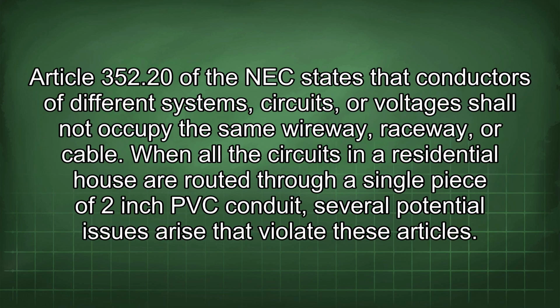Article 352.20 of the NEC states that conductors of different systems, circuits, or voltages shall not occupy the same wireway, raceway, or cable. When all the circuits in a residential house are routed through a single piece of 2-inch PVC conduit, several potential issues arise that violate these articles.